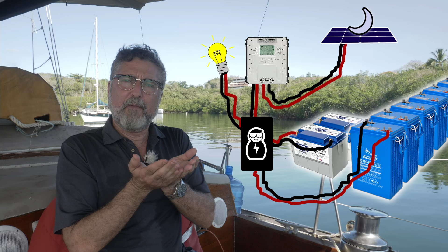What it does is, overnight your batteries are together. Throughout the day - I'll say day because almost everybody now charges with solar - power's coming in, and the voltages of the batteries are locked together, they come up together. When they reach a point where you'd like your lithium to stop charging, the system breaks them apart. The lead is still connected to a charge source and continues to rise, and the solar regulator is in control of the lead and does whatever's necessary.